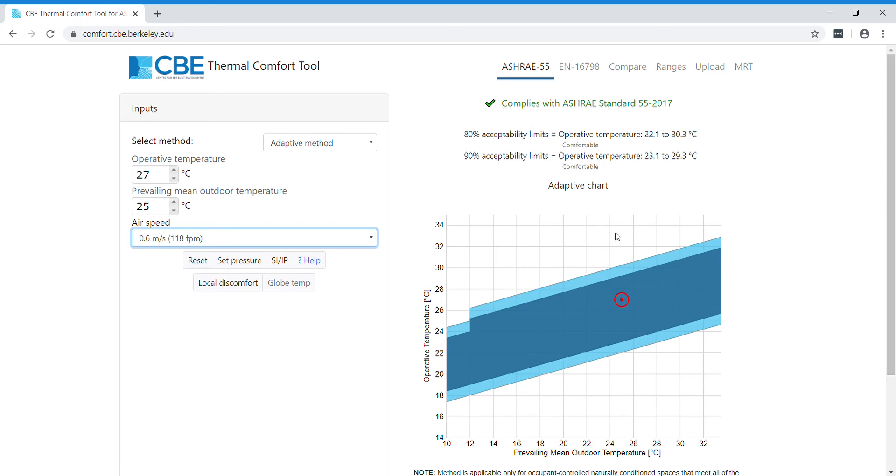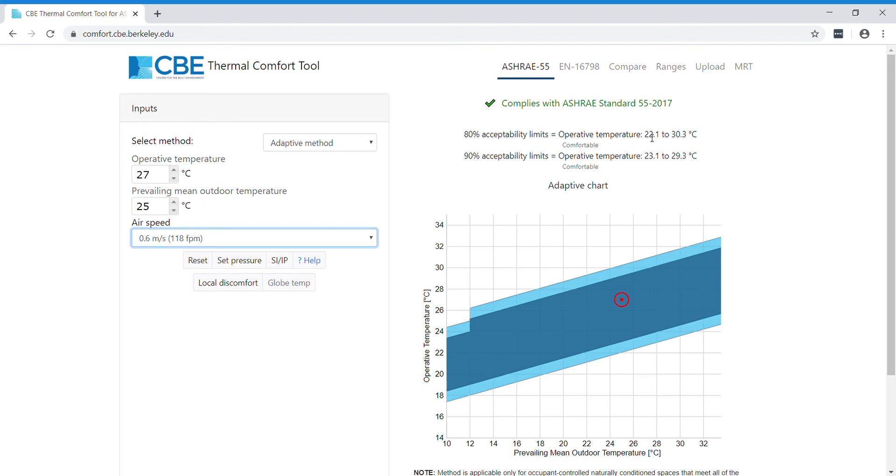For instance, in this case, we are within both the 80% acceptability limit and the 90% acceptability limit, so we are complying with the ASHRAE 55 standards. This also tells us the operative temperature range needed.